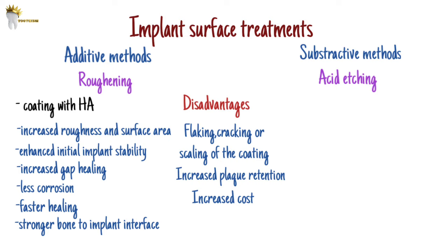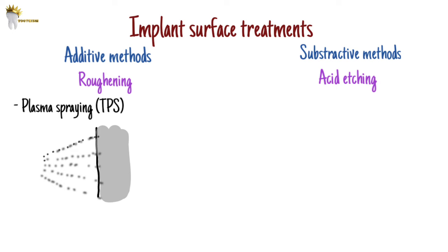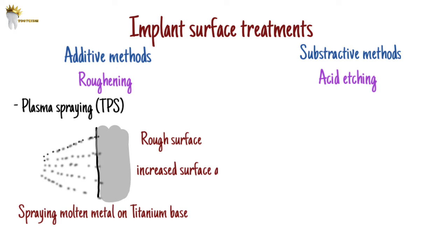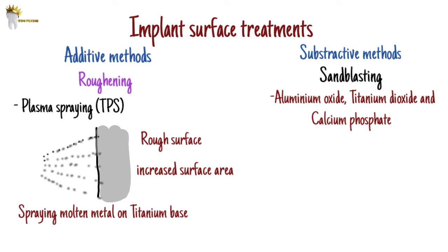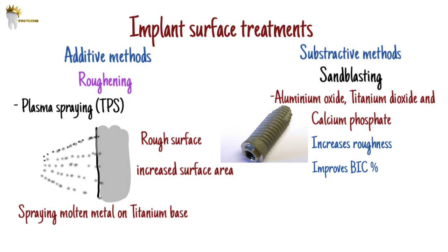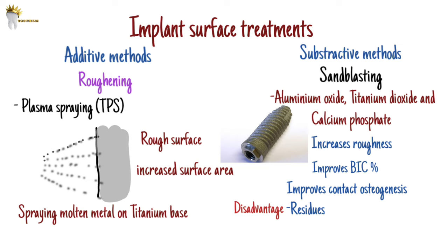Titanium plasma sprayed surface (TPS) is prepared by spraying molten metal on the titanium base, resulting in a surface with irregularly sized and shaped valleys, pores, and crevices. This increases the microscopic surface area by approximately 10 times. Sandblasting is done using agents such as aluminum oxide, titanium dioxide, and calcium phosphate to increase surface roughness. Sandblasting not only improves bone-to-implant contact percentage but also improves contact osteogenesis by allowing the adhesion, proliferation, and differentiation of osteoblasts over the implant surface. The disadvantage is that there could be residues of sandblasting materials, and it could be non-uniform and result in loss of metallic substance from the implant.